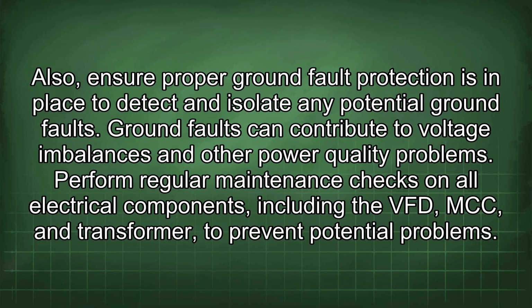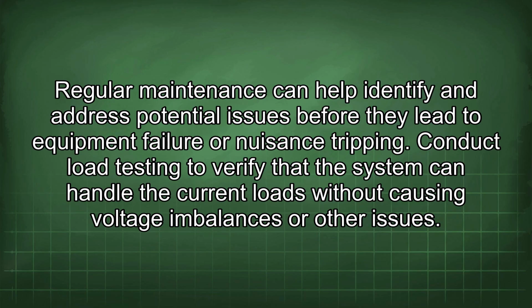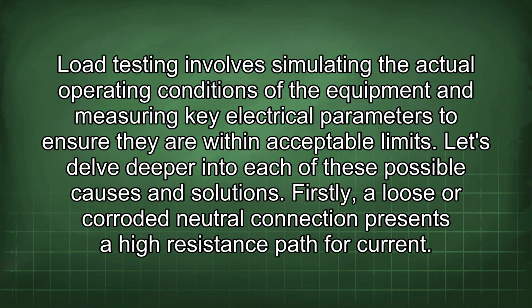Perform regular maintenance checks on all electrical components, including the VFD, MCC, and transformer, to prevent potential problems. Regular maintenance can help identify and address potential issues before they lead to equipment failure or nuisance tripping. Conduct load testing to verify that the system can handle the current loads without causing voltage imbalances or other issues. Load testing involves simulating the actual operating conditions of the equipment and measuring key electrical parameters to ensure they are within acceptable limits. Let's delve deeper into each of these possible causes and solutions.